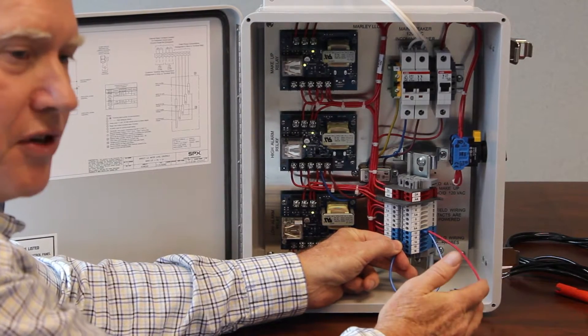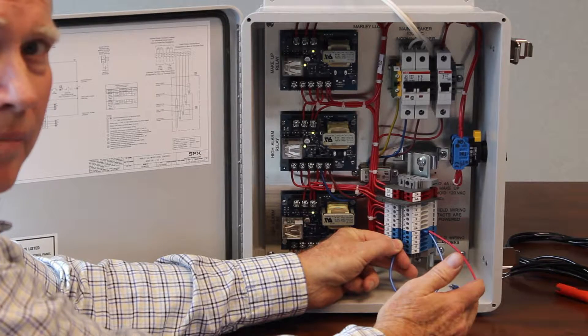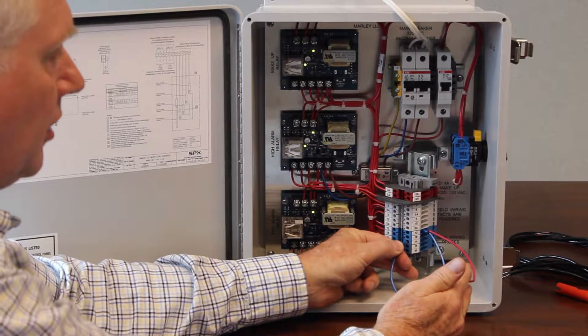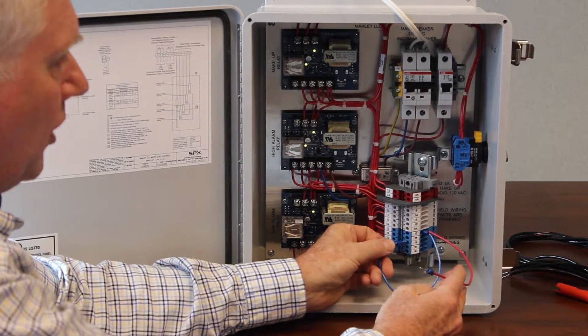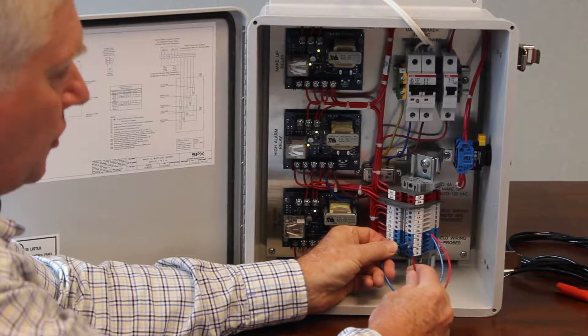Now, as you notice, nothing has happened yet — that's okay, because water is rising, it's making up. The water is rising above 14, and when it touches the higher probe, which is probe number 15, it's going to turn off.